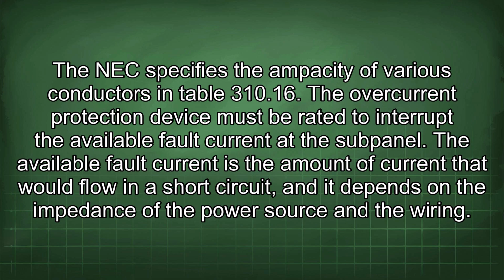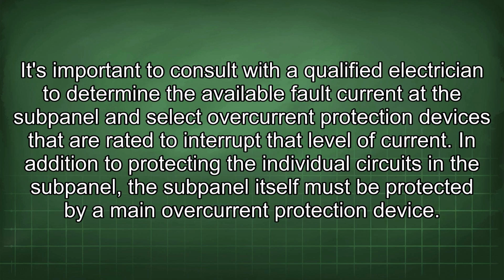The overcurrent protection device must be rated to interrupt the available fault current at the subpanel. The available fault current is the amount of current that would flow in a short circuit, and it depends on the impedance of the power source and the wiring. It's important to consult with a qualified electrician to determine the available fault current at the subpanel and select overcurrent protection devices that are rated to interrupt that level of current.